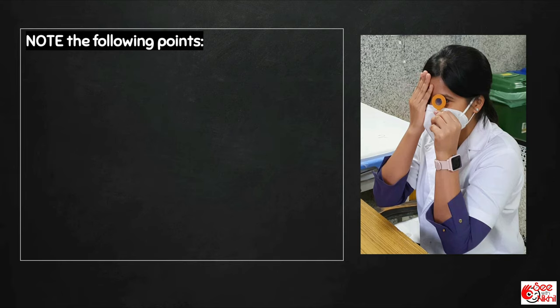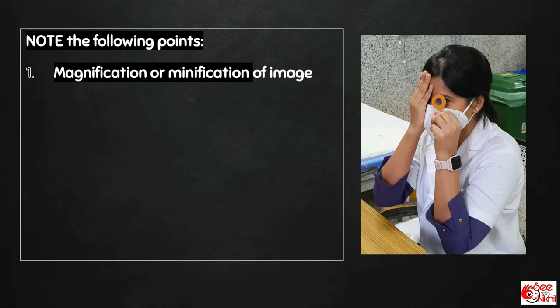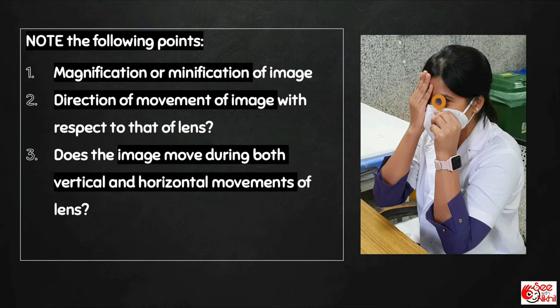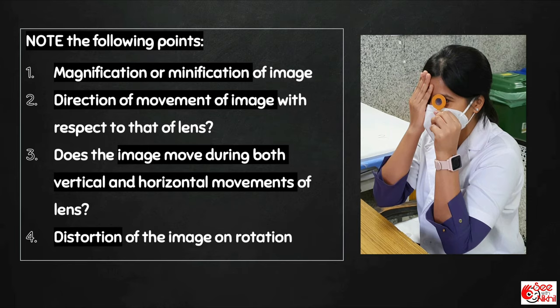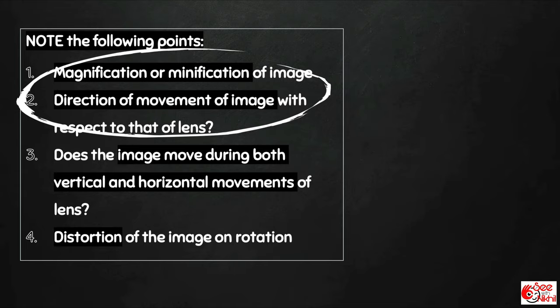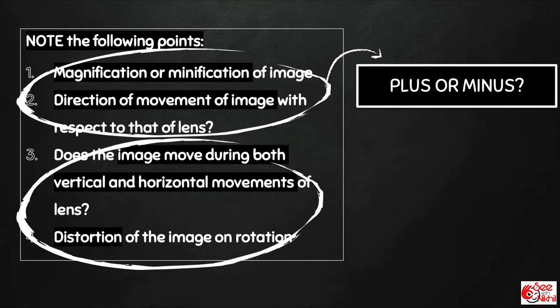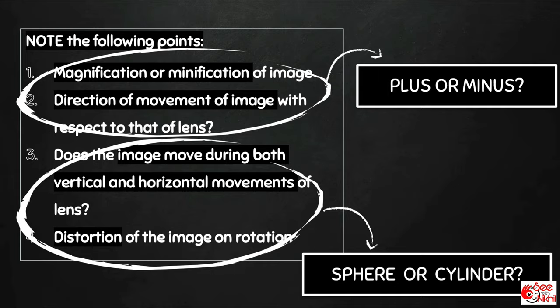Then move the lens in vertical and horizontal directions and then rotate the lens. Note the following points: Is there any magnification or minification of image? What is the direction of movement of the image with respect to that of the lens? Does the image move during both vertical and horizontal movements or only during one of them? And is there any distortion on rotation? The first two points will tell us if it's a plus or minus lens, and the next two will tell us if it's a sphere or cylinder.